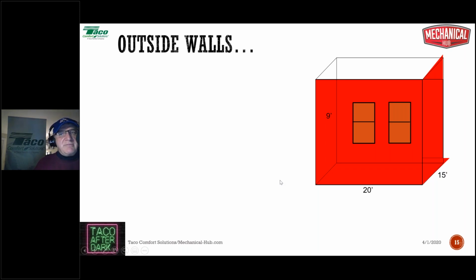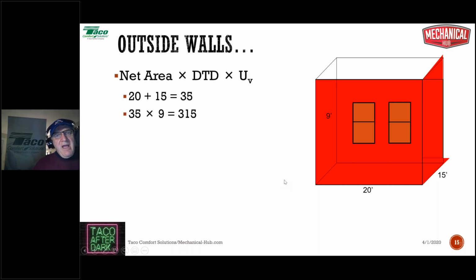We're looking at outside walls. According to this, our room has two outside walls: one of them's 20 foot long and one of them's 15 foot long. Our formula for walls is length times width, it's area, but in this case we're going to be talking about net area. Net area, so basically taking out everything we've already done. In this case, it'll be the windows. If there were doors, we'd take the door area out too. So it's net area times design temperature difference times the U value of the wall assembly.